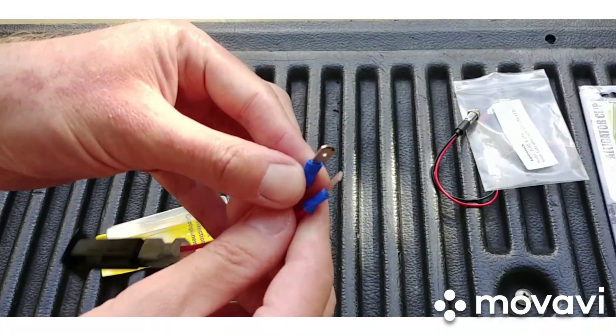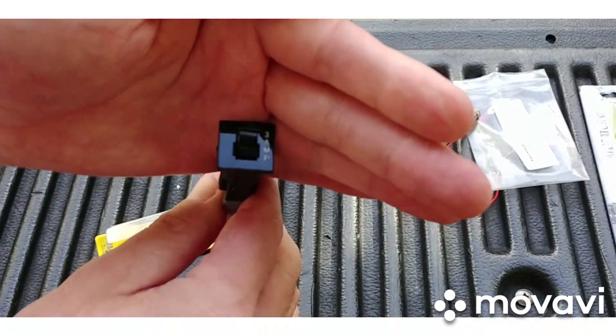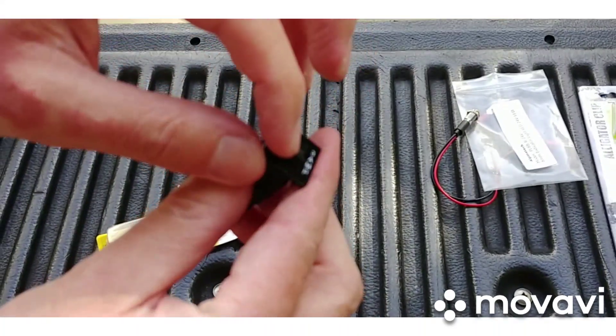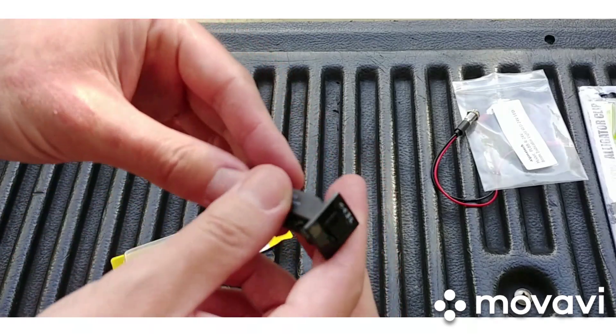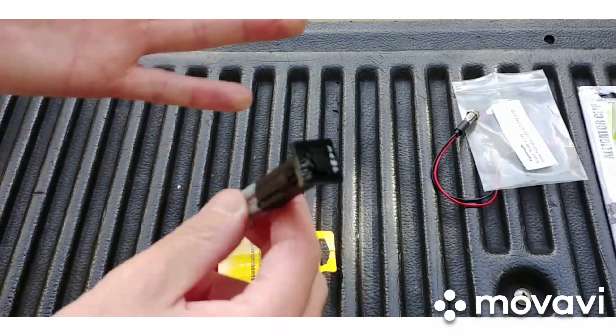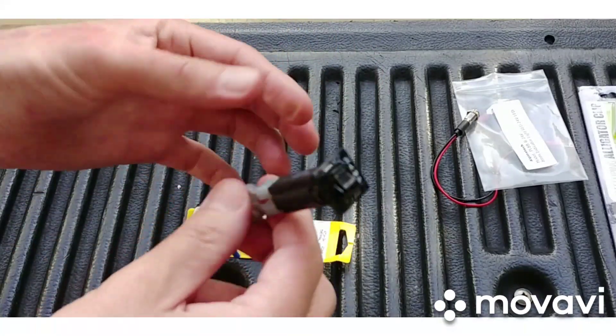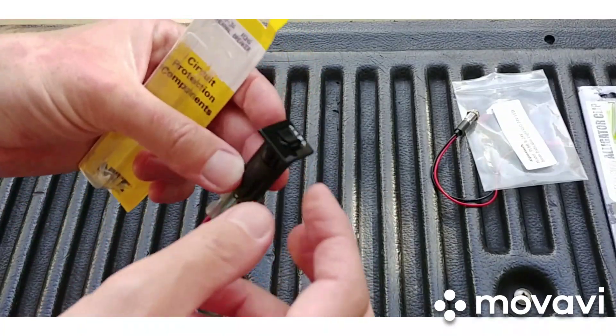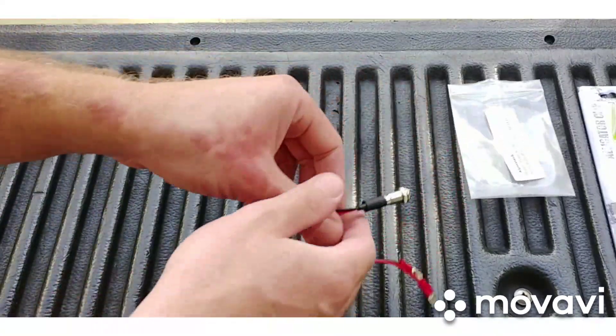I added these wires — male spades and female insulated spades. They also sell five-amp versions. When this blows, the switch will turn white. It's resettable, which is cool if you have a unit that blows a fuse now and then and it's a hard short to find — you could install this permanently. A lot of carrier package units have these, so if you're going to scrap one, I highly recommend harvesting these out before it goes to the scrapyard.